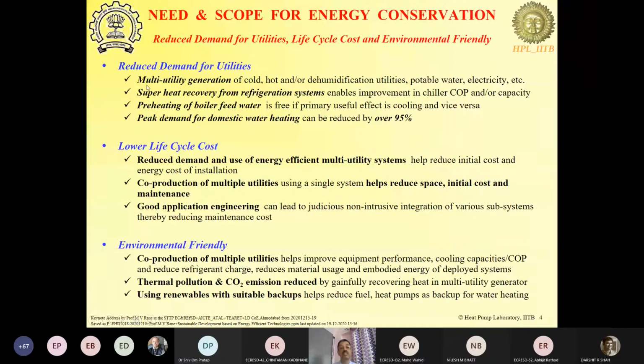In this, we can see the multi-utility generators: cold utility, hot utility, the dehumidification utility, potable water generation as a utility, electricity as a utility. So, can a single system generate more than one? Now, when we talk about an air conditioner, it typically only generates cooling. A heat pump water heater only generates hot water. A boiler only generates this. A DG set only generates electricity. So instead of doing that, can we have a DG set and recover the heat from the exhaust, and then that recovered heat can be used for dehumidification, or for potable water generation, and so on and so forth.